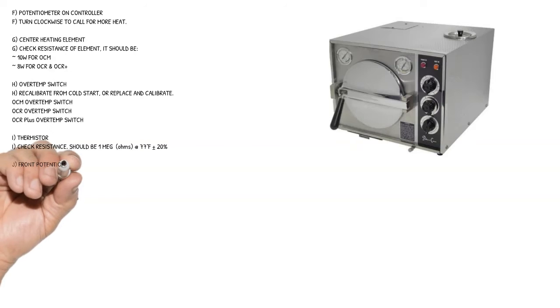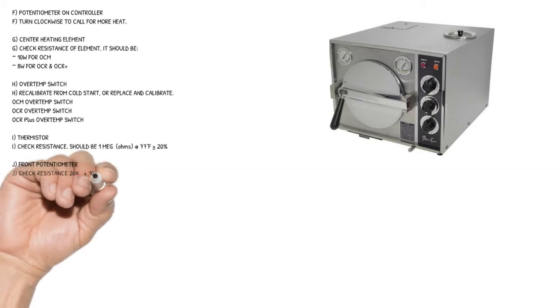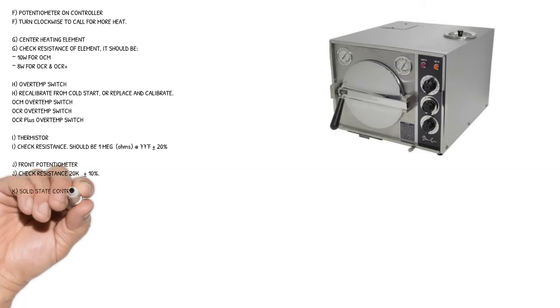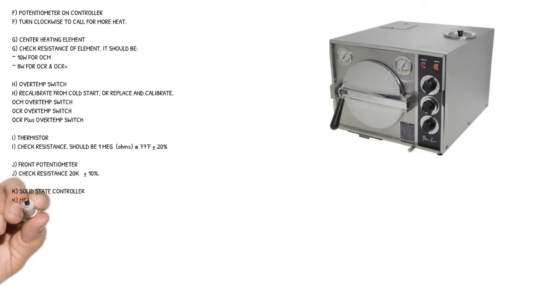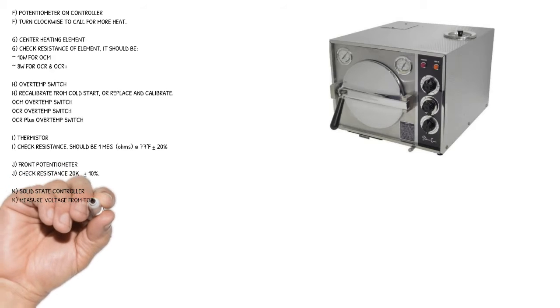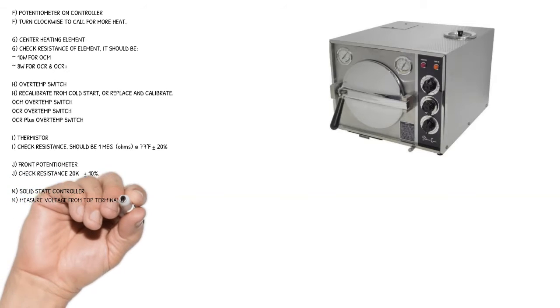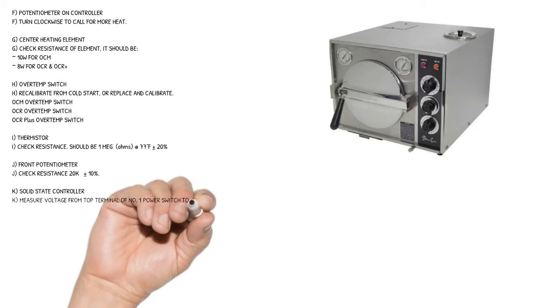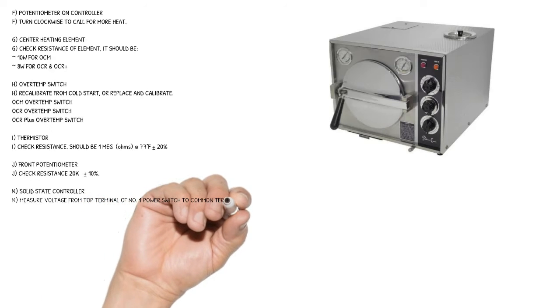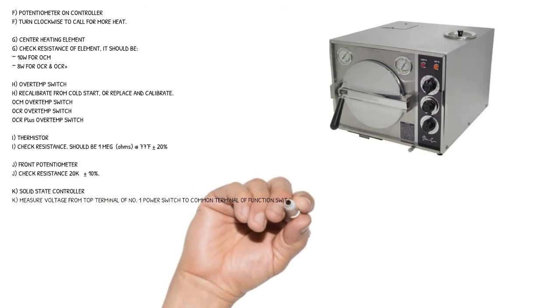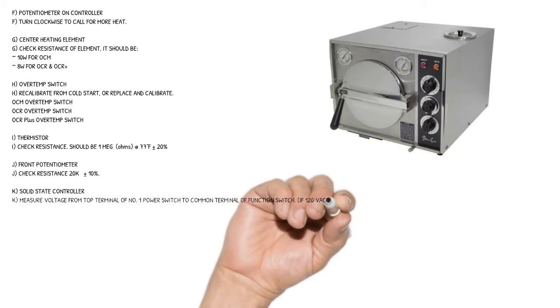Cause I: thermistor - check resistance. Should be 1 megaohm at 77 degrees Fahrenheit plus or minus 20%. Cause J: front potentiometer - check resistance 20k ohm plus or minus 10%.